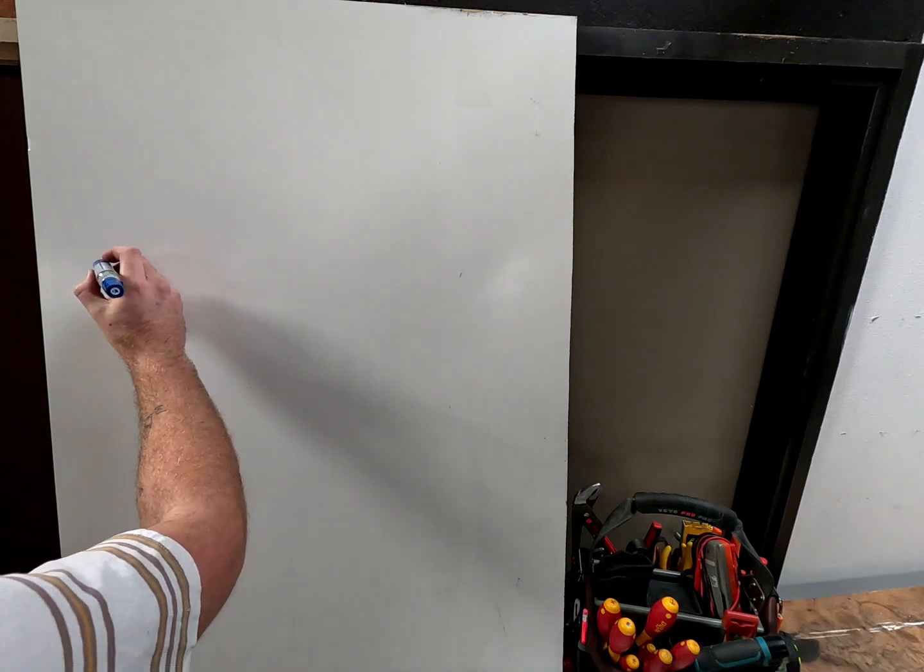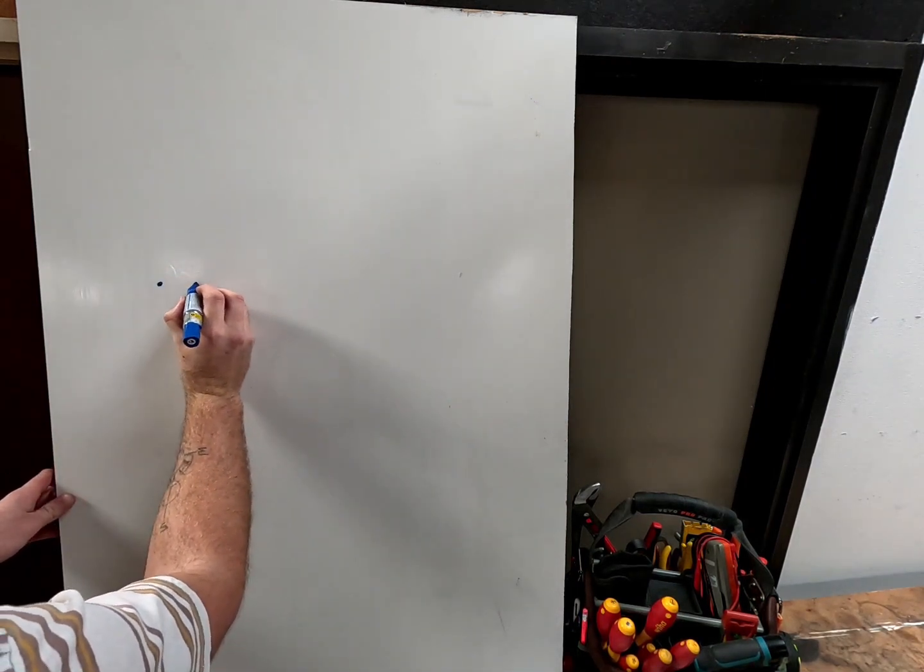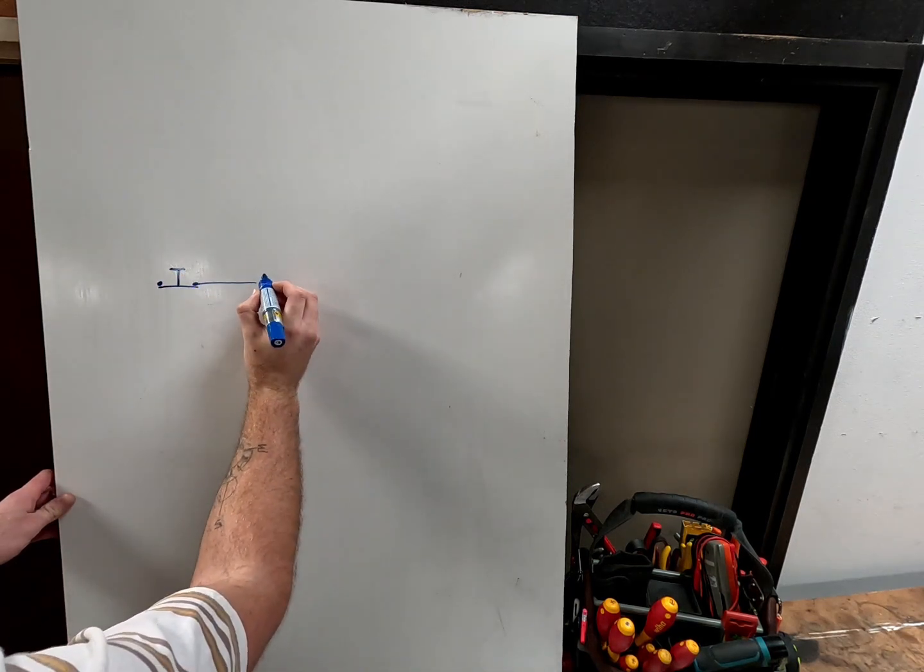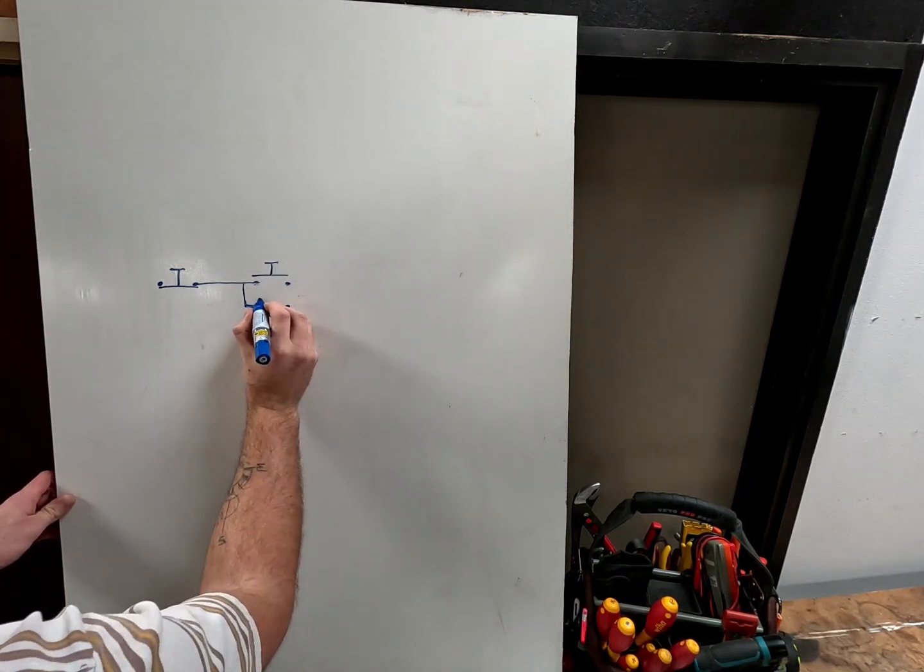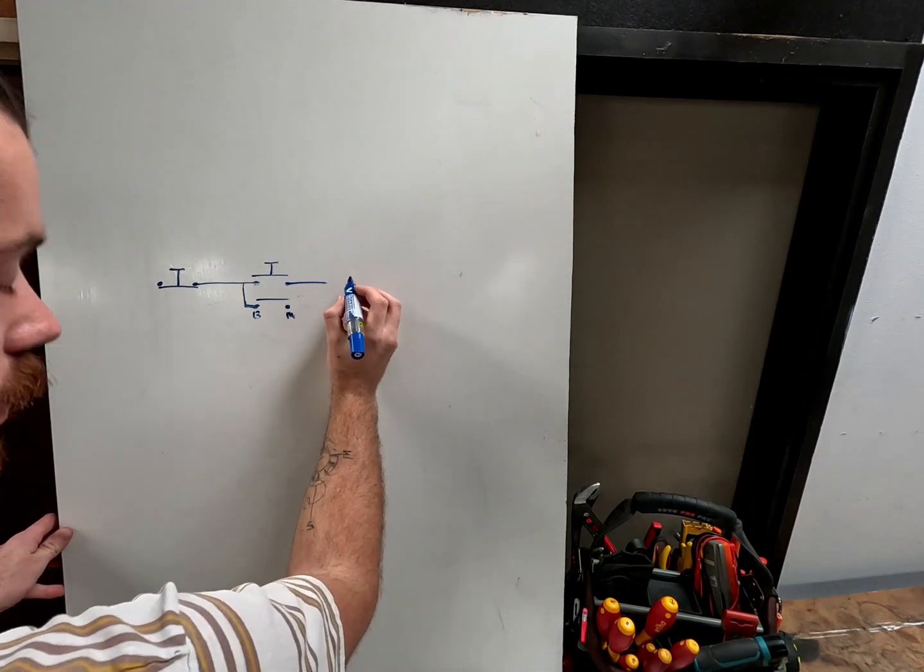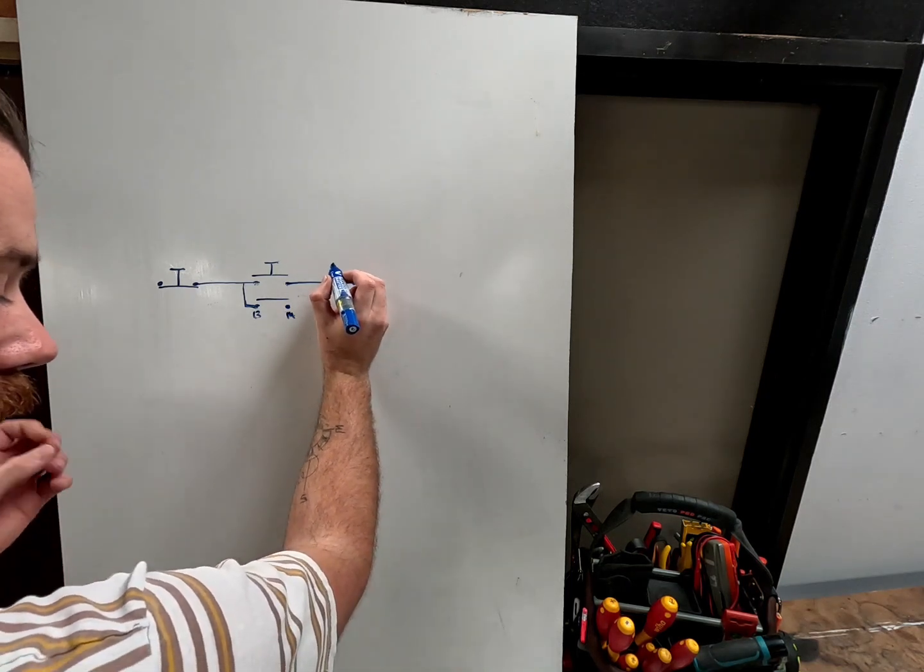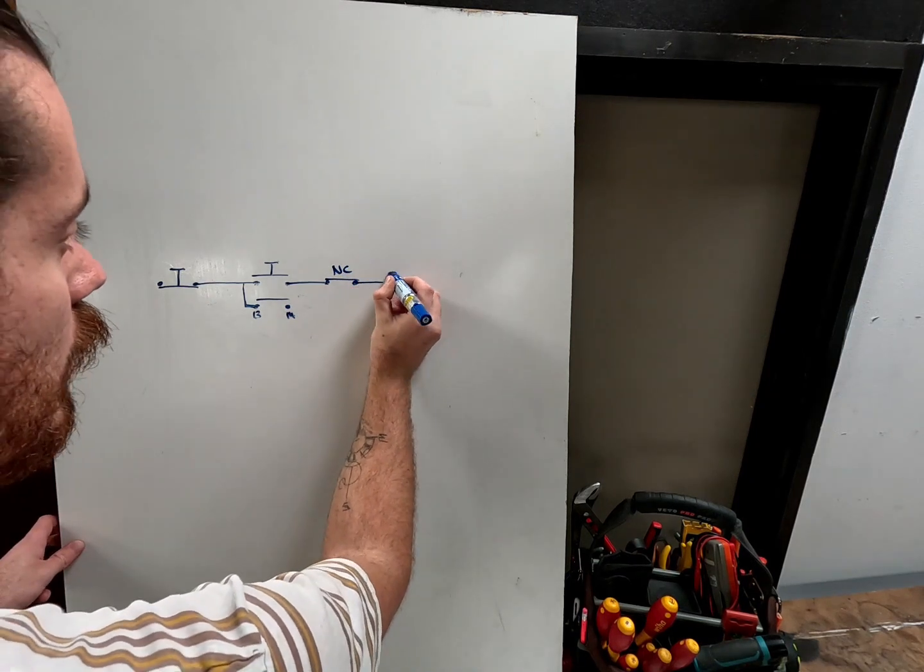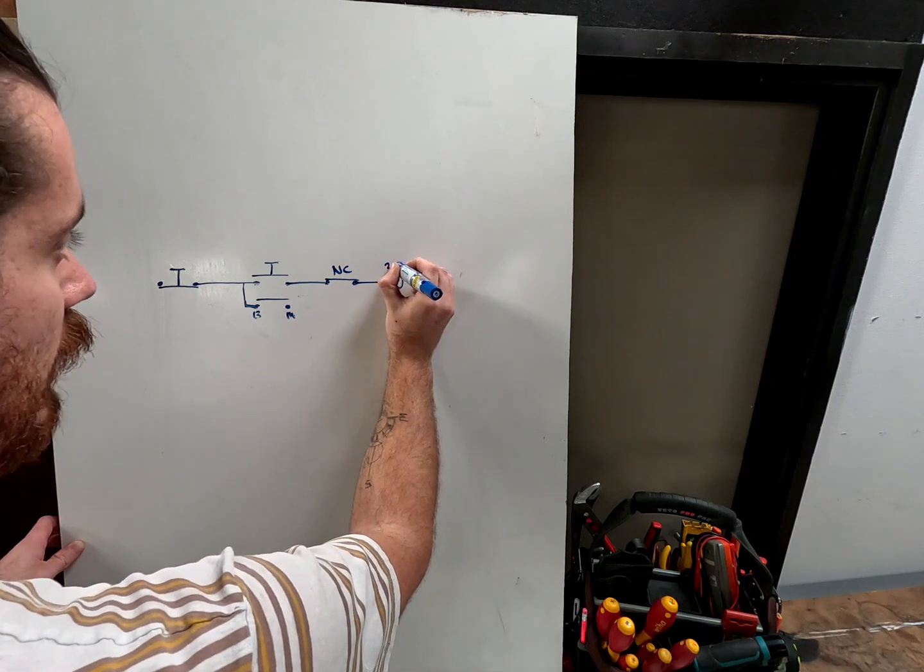On the top set of contactors we're going to have a stop button, a start button, goes to the auxiliary. We'll then go to an overload, which if you remember from last video is also a stop button. It's normally closed and then it will go to the coil. This first one is going to be the 24 volt coil.